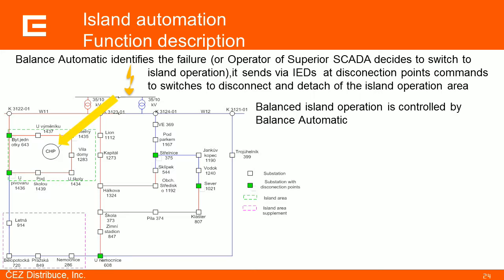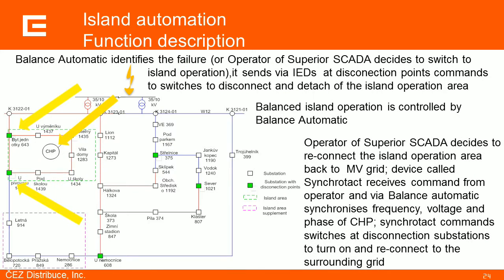The balance automation disconnects the island operation area from the rest of the grid and ensures that the power production and power consumption at the moment of island operation are balanced. Once the failure is fixed, or once the operator of the superior SCADA decides that it is time to switch back to standard conditions, the balance automation and the equipment called Synchrotact, which is responsible for synchronizing the phase, voltage and frequency of the CHP, provide the synchronization, and the island operation area can be connected back to the grid.